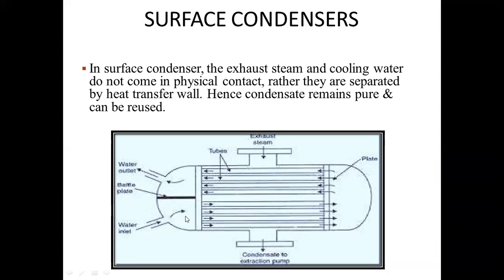So cooling water is inside the pipe while exhaust steam is outside the pipe. Cooling water moves from this pipe to the shell to the pipes, and then it moves outside, while exhaust steam comes in contact with the pipe. It releases its heat, and it comes downward from where it can be removed.